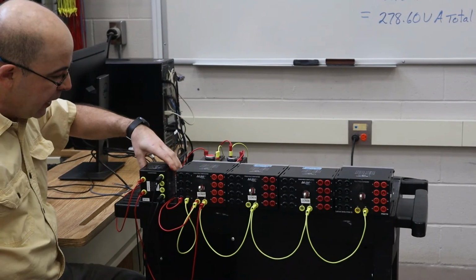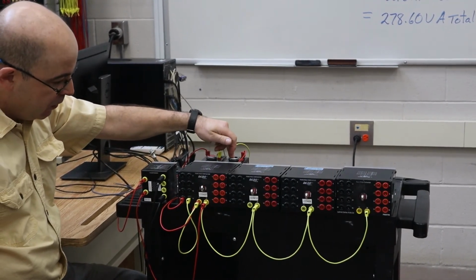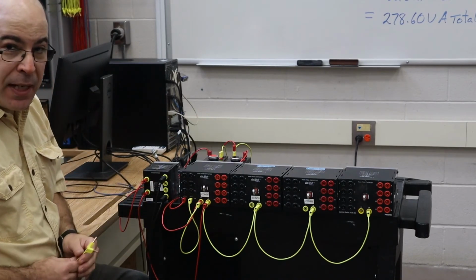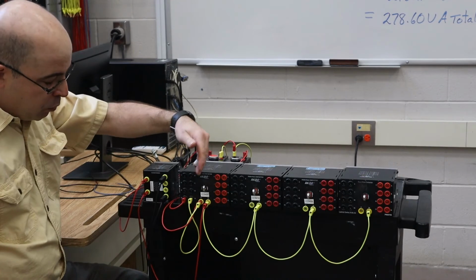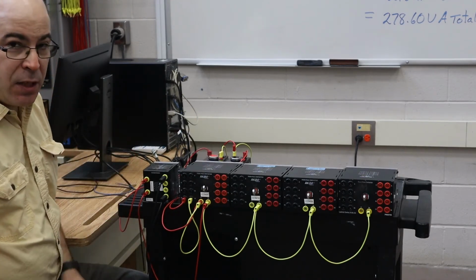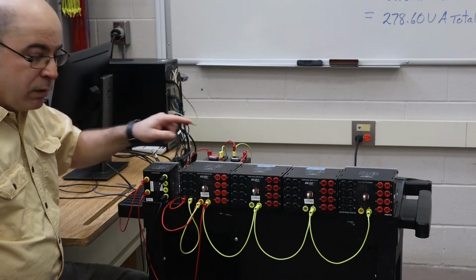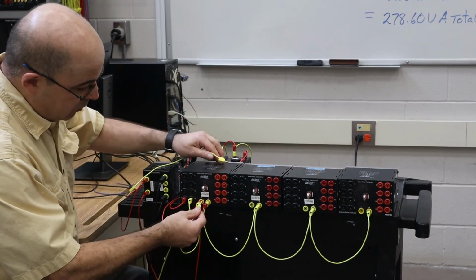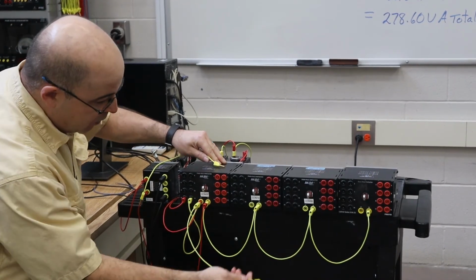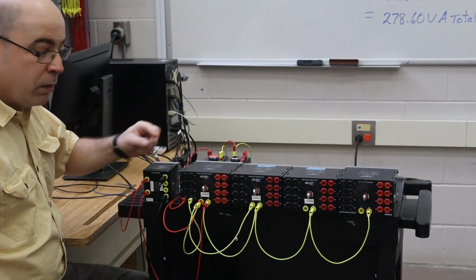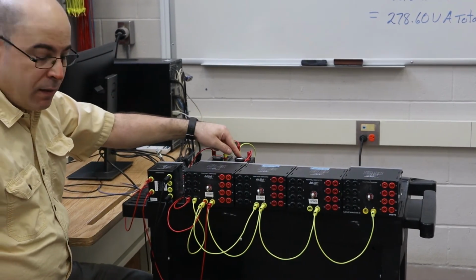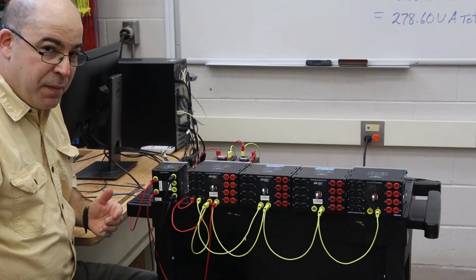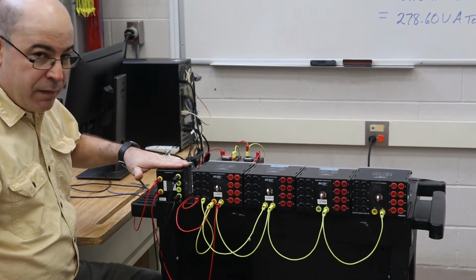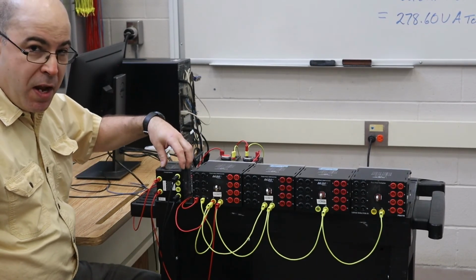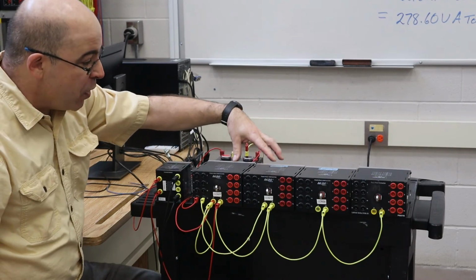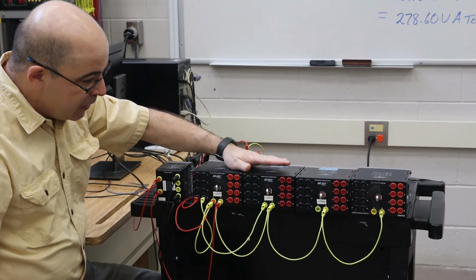So here goes. With a single relay in my control circuit, I'm going to energize the circuit, and you can see the same thing as happened before. The one armature has pulled in, no big noise, everything is working the way it should be. Let's drop that out and add that second relay. And we're going to piggyback onto this one. Now, with two relays in my control circuit, let's energize. Now, this is where things fell apart the last time because the 25 VA control transformer could not deliver enough apparent power for the inrush for both of my relays. And you can see everything's working just nicely.